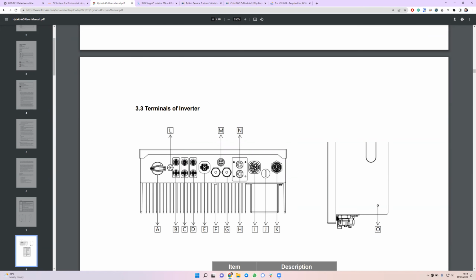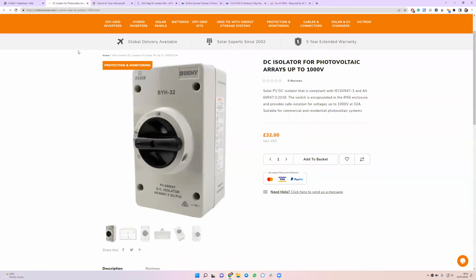If it's on the inverter, you'll hear a click, and then it will return back to its default position. You'll feel the spring. You've got to push it all the way till it clicks, and then release it. And then you'll notice that the DC is then working. The solar. If you've isolated it here and you've not done it on the inverter, just turn the switch back to on. You'll hear a clonk. Don't be timid. You've got to turn these isolators with some force, and you've got to do it quickly so that it makes a good contact.